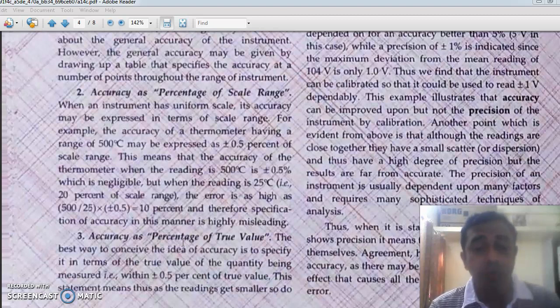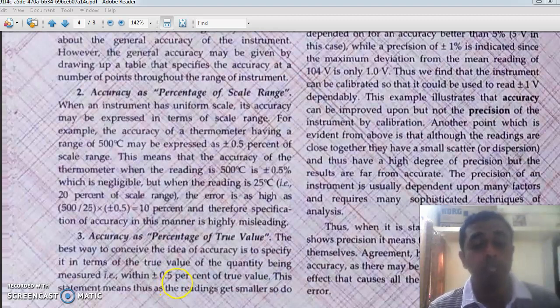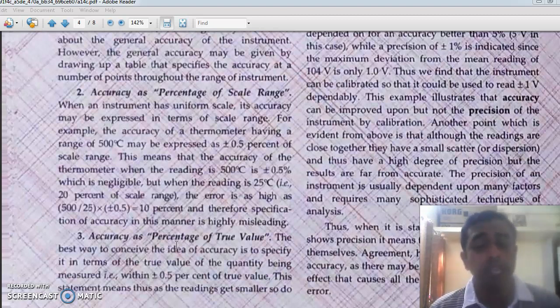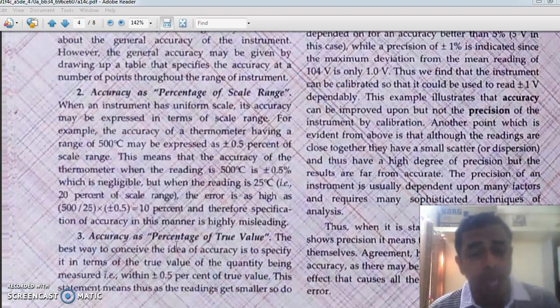Rather, we specify accuracy as the percentage of true value. If you do that, then as the reading reduces, the true value also reduces, so the percentage error also reduces — that is, plus or minus 0.5 percent of 25 degrees Celsius is a very small quantity, rather than 10 percent. This is the common way of representing accuracy as percentage of true value. In lab class also, while we draw the calibration curve, this is how we calculate the accuracy or percentage error.